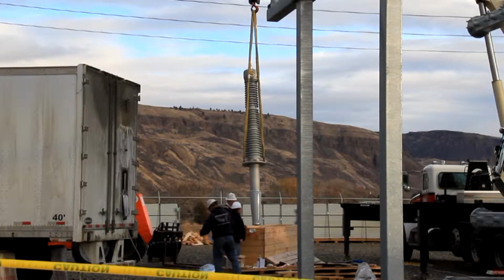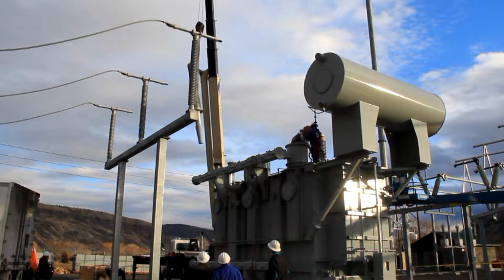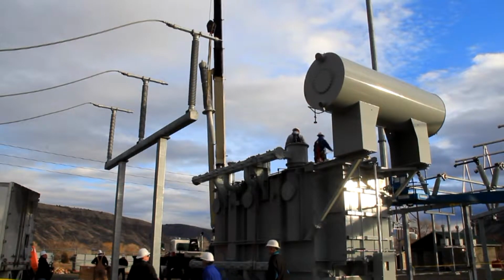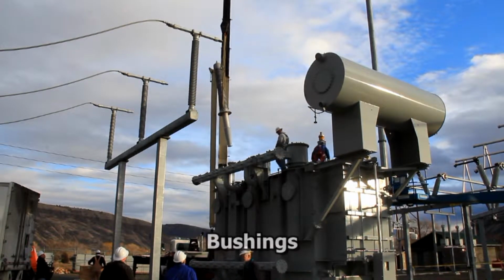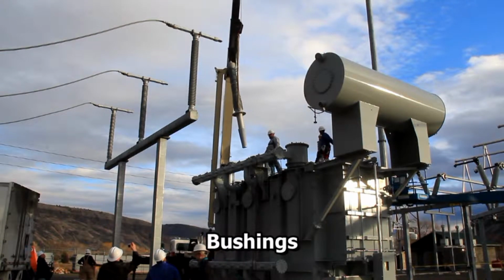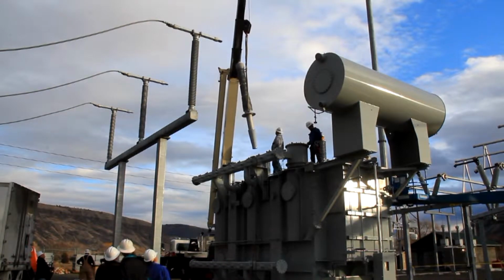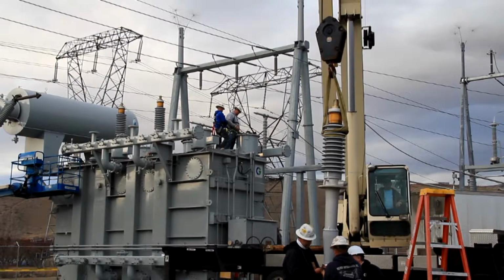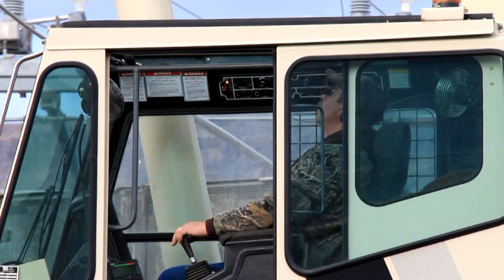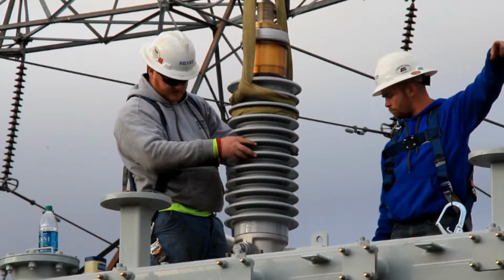Throughout the week, we will be installing the bushings, which are insulators where the connections to the transformer are made, to both the high side, in this case 230,000 volts, and the transformed voltage of 115,000 volts, which will be used for our main service areas in Douglas County.